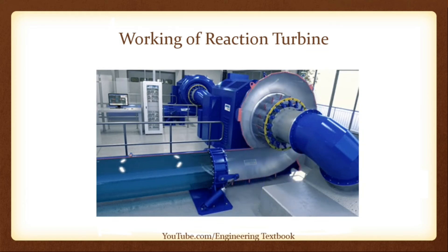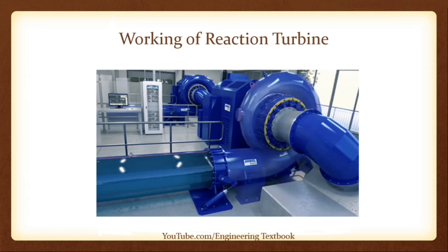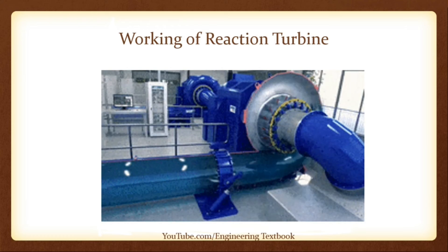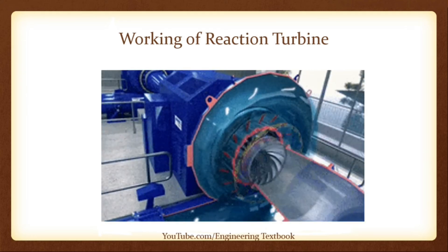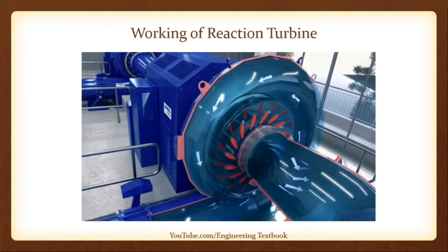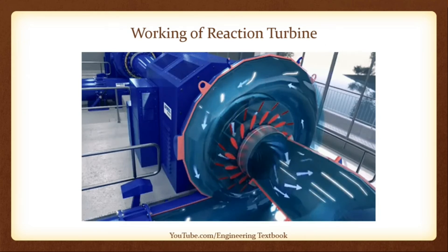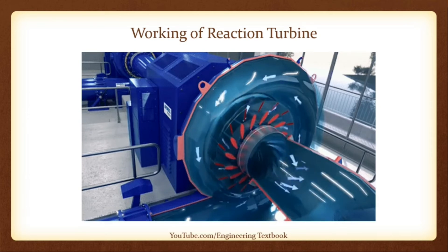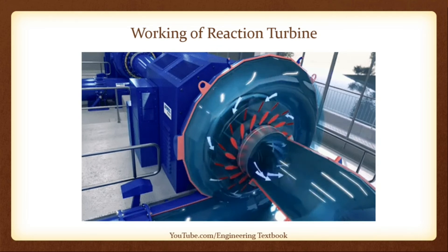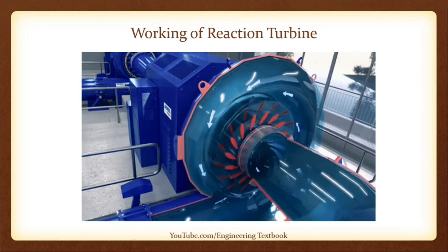Low head, high velocity water enters the spiral casing. As it enters the casing, it starts flowing through guide vanes into the runner blades. These guide vanes direct the flow of water to strike the runner blades at a proper angle to produce maximum power output. The water flowing through the spiral casing maintains consistent pressure throughout the circumference due to the uniformly decreasing cross-sectional area. The guide vanes can change their angle to increase or decrease the flow rate of water into the turbine.